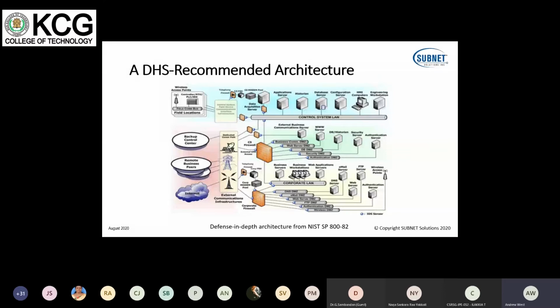Some people like to, and especially in the IT space, they would prefer to put intrusion prevention systems, IPSs. I think there's risk in doing that in a control system because there are some times when there is an unusual message which is required for an emergency situation, like a shutdown message, that would possibly be blocked by the IPS. And because it's an unusual message, it thinks it's an attack. So there's a lot of decisions to be made during cybersecurity design.